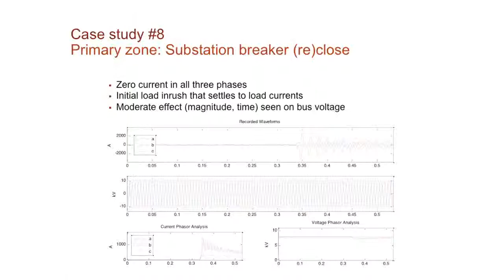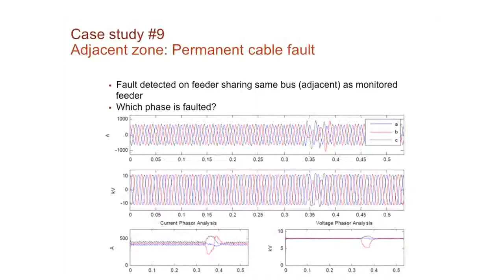Now, this is an adjacent zone. Remember I said, so we're at the same feeder, but now it saw some current and voltage activity. And it sent that data to the substation computer, COM600, that evaluated what kind of feeder event it was. So when it came out, it said it was an adjacent zone fault, permanent cable fault. So this is the kind of limited information we have, but yet we say it's an adjacent fault. We're seeing it, so we must be on the same bus. The feeder's on the same bus. And then with that dip in voltage, short-lived, that tells you that fault was on that phase.